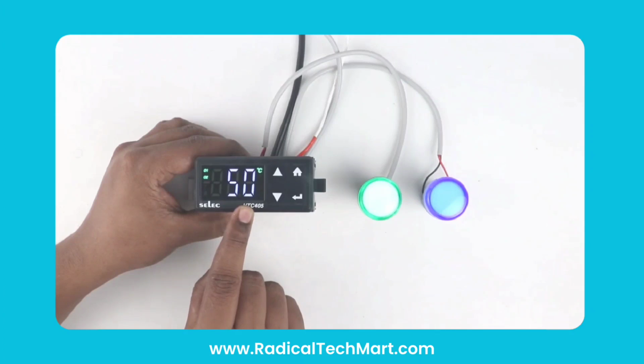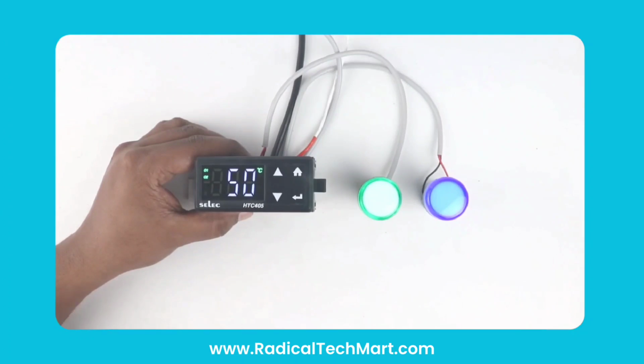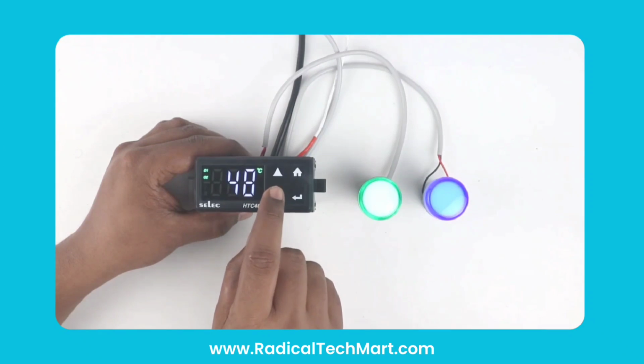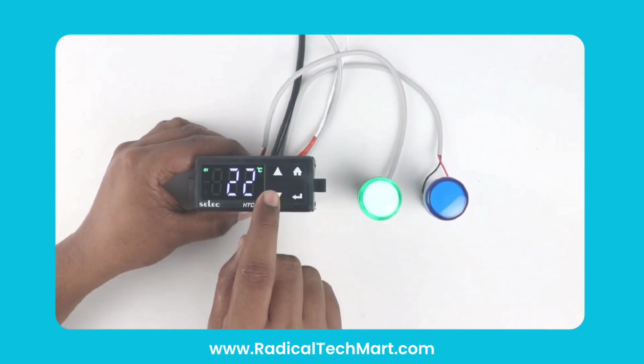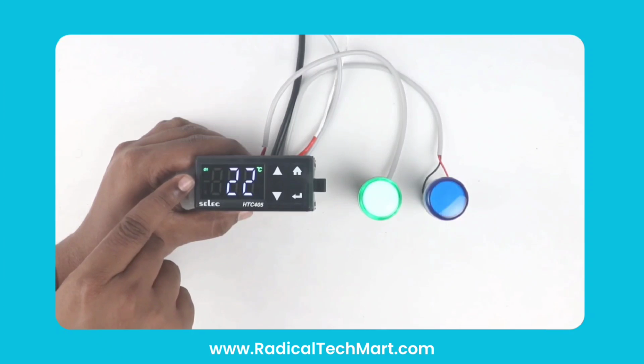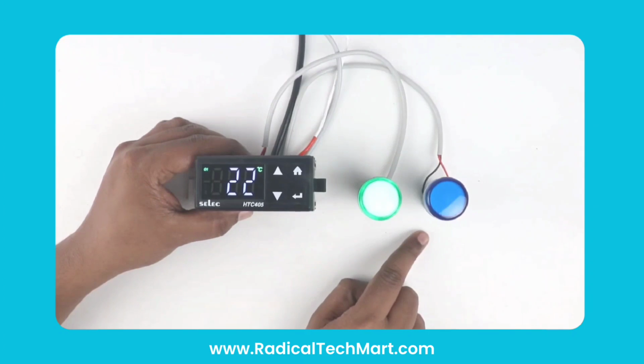Similarly, to change the temperature set point, press Enter twice. The degree Celsius symbol appears, indicating editable mode. If I set the temperature to 22 degrees, the output turns off because the actual temperature is 23, which is above the set point.